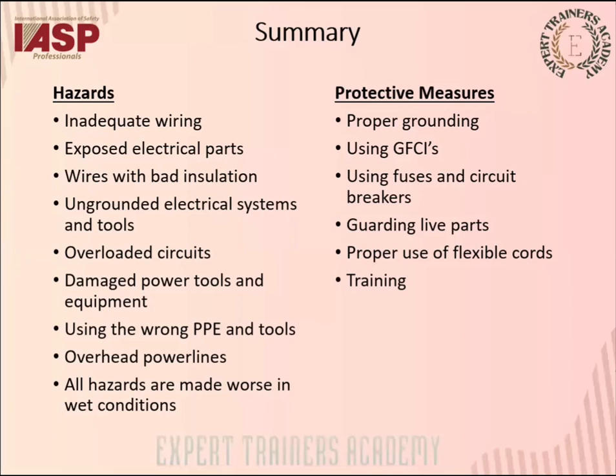So what are the protective measures that we can use? We can use proper grounding. We can use GFCI. We can use RCD. We can use MCB, fuse, earthing, double insulation. And all the electrical works like inspection and maintenance must be carried out by a competent person. Whenever you're working with any overhead lines or you're excavating certain ground which has electrical cables, you must use a safe system of work and permit to work before doing so. So these are the things that we can do to protect ourselves. So that's about it for this topic.